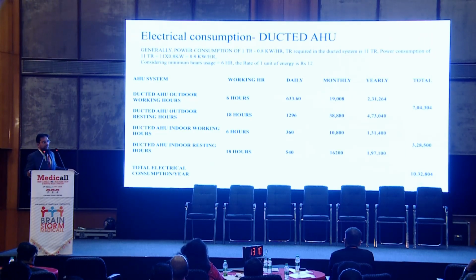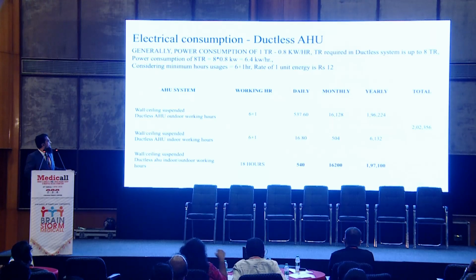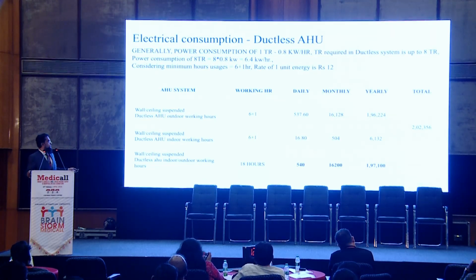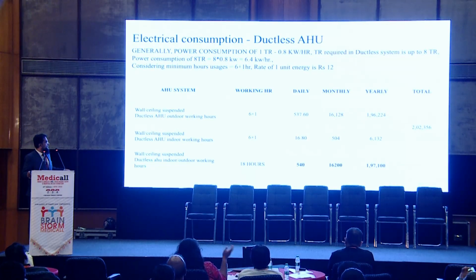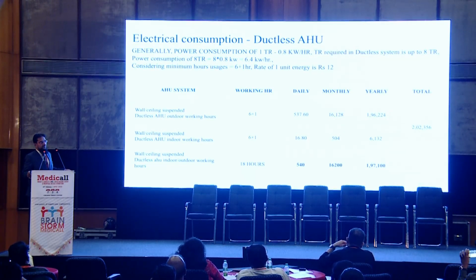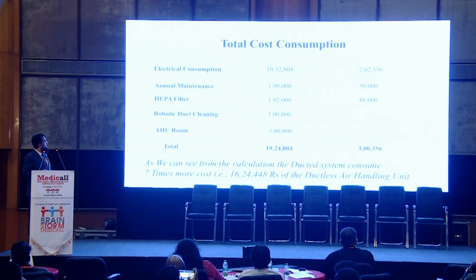So it comes to 10,32,000 in a year. With my systems, I had calculated 1 hour before you have to start, so for getting the 20 air changes you required 1 hour. Even with that 1 hour added, the electrical consumption comes to 2,02,000. So you are going to save how much in the electricity? 8,30,000.